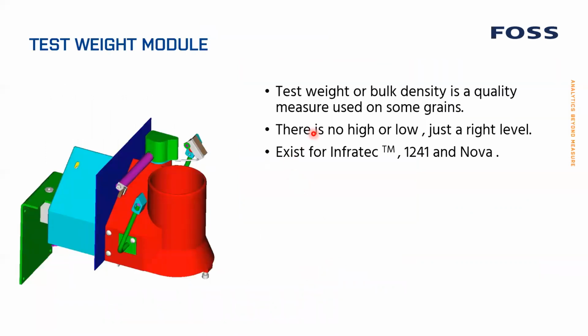The test weight module, test weight or bulk density, is a density meter. It's a cup with a lid at the bottom, so it will close and be filled up with grain. It's actually topped up, and then there's an arm that sweeps it off, so it's always filled to the same level. It measures the weight and calculates the density, or what's called the test weight. There's no high and low on a test weight. It's just the right level. When you have different grains, they should have a certain test weight. And you can have that for the Infratec TM, 1241, and Nova, not for Sophia.